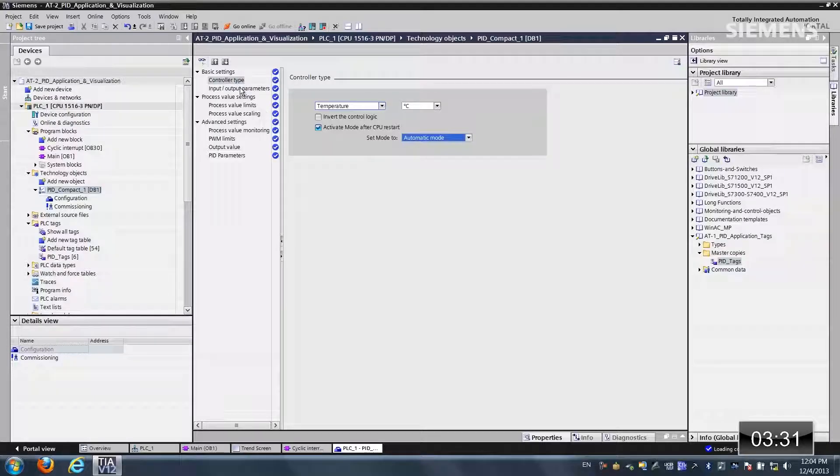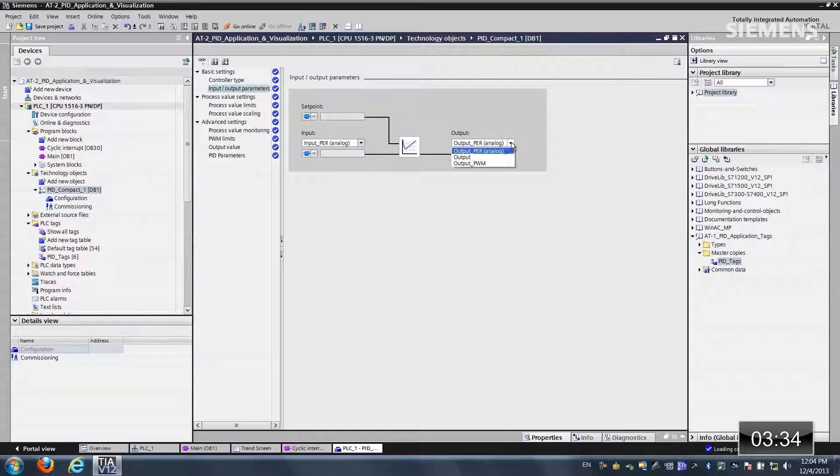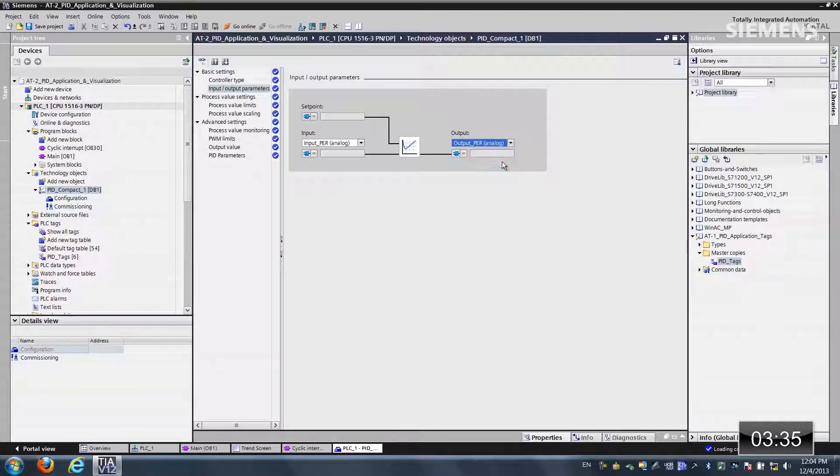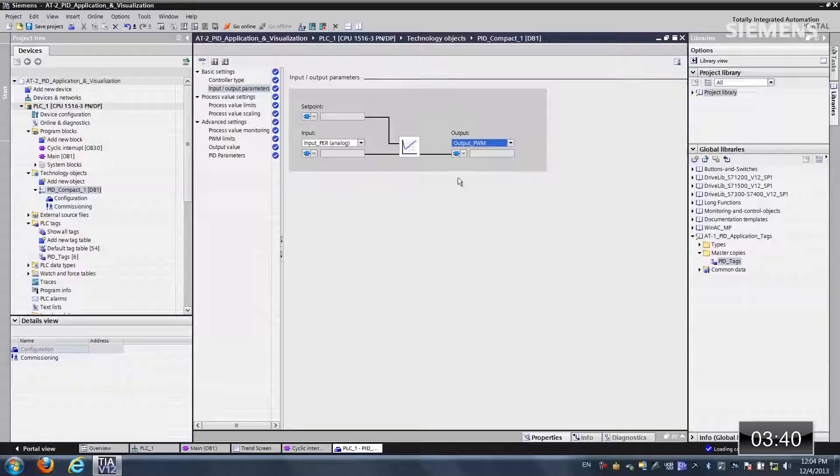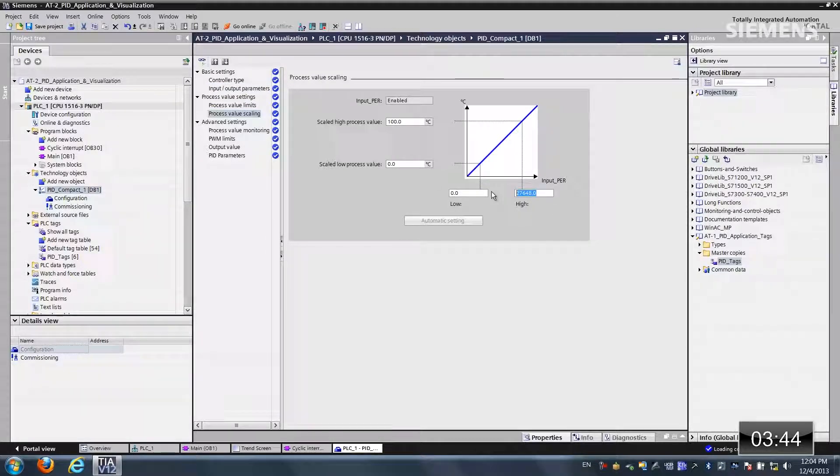The next thing I like to do is input output parameters. On the output side, I want to change it to output PWM because we're going to do a pulse train output for this resistor, this heater. Now I want to go down to the process value scaling, and I want to change this high to 1000.